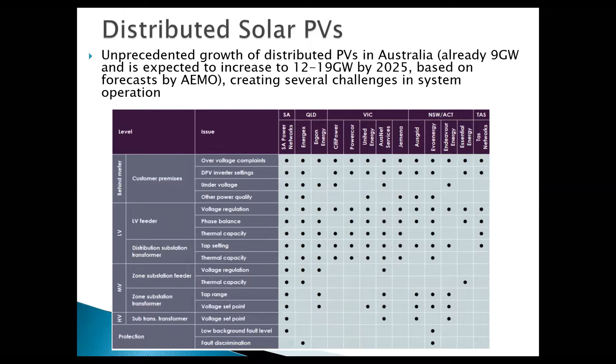Similarly there's a problem because of tap settings. Oftentimes the tap settings were on manual control, or sometimes automatic control, but these controls are time-based. That means at 6 o'clock in the evening the tap setting changes because they know the peak load will come, and you improve the voltage in the distribution system using a tap-changing transformer. However, now the problem is otherwise, because of very low load, meaning very high voltage in the daytime, so now you actually have to lower the tap to control the voltage.